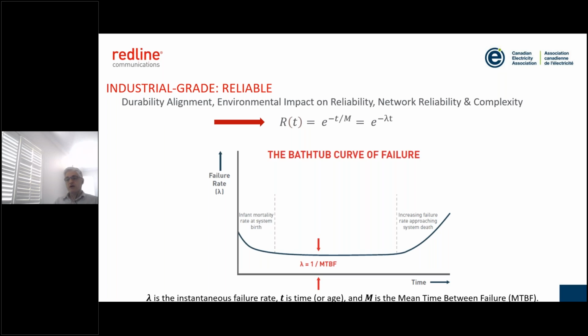The problem is we forget that the MTBF calculation the manufacturer does is based on an assumption of ideal conditions. The equipment is designed for specific conditions in mind - let's say temperature, a simple criteria - it's designed for a specific temperature range. If you deviate from that range, the failure rate is going to shoot up. The MTBF is no longer valid.